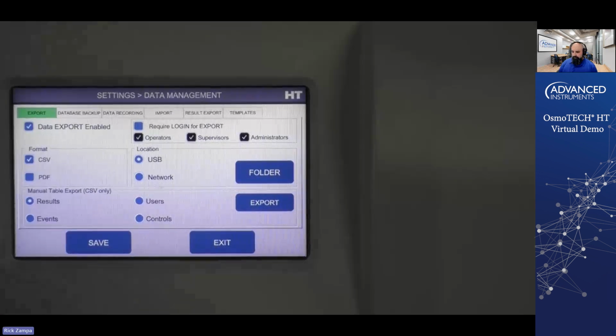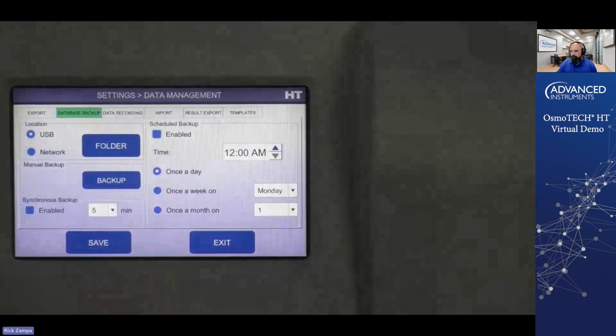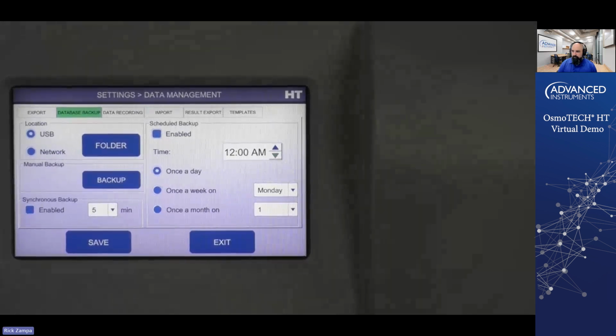If you're going to set up your system to automatically export the data, that would be done through your local area network or your ELN, and I'll show you where that is in a second. We also have a database backup function. The difference between the database backup function and exporting the databases out is that the database backup function actually backs up the configuration files as well.